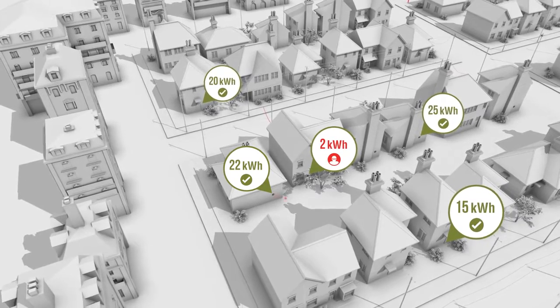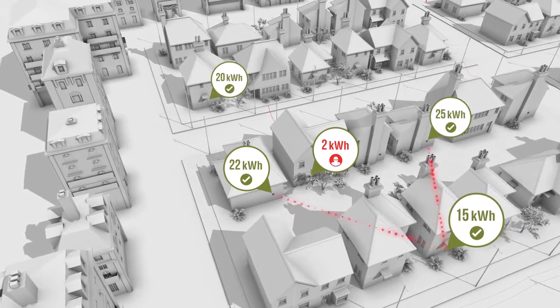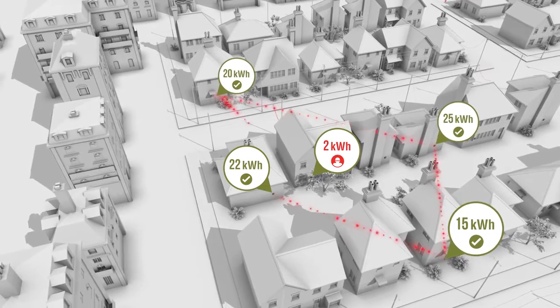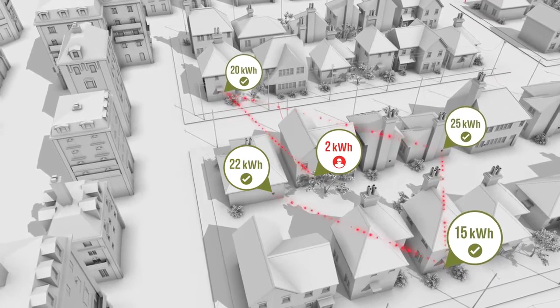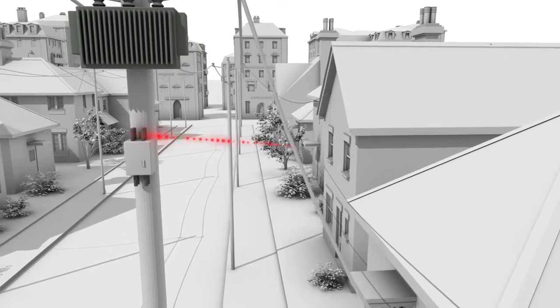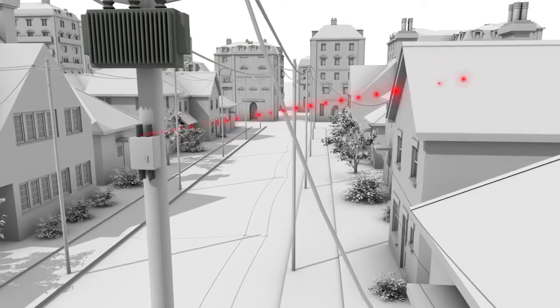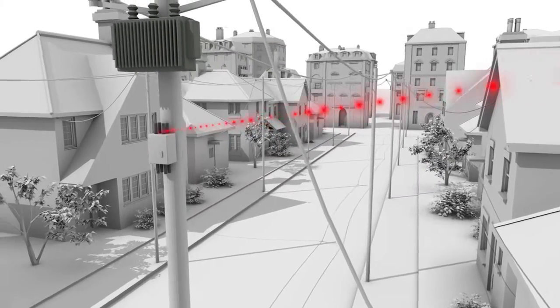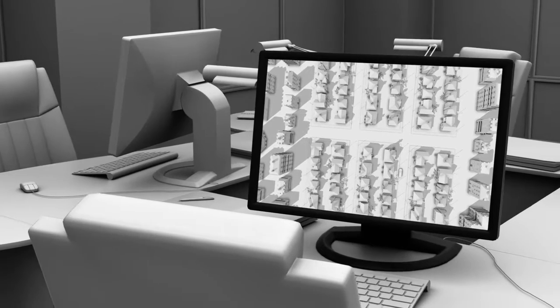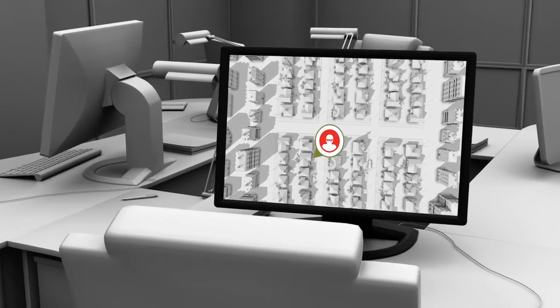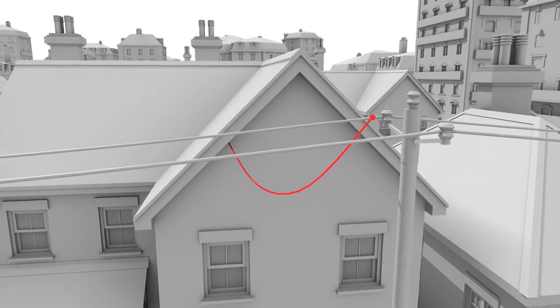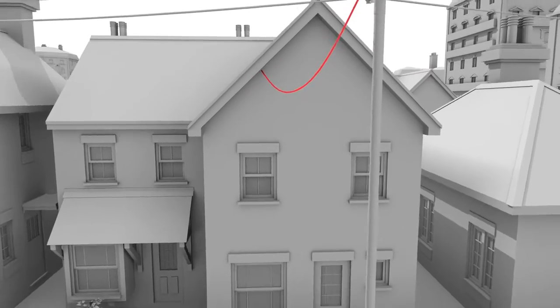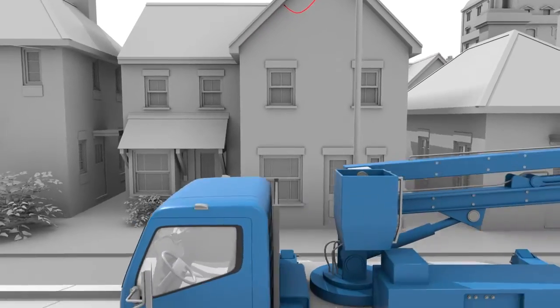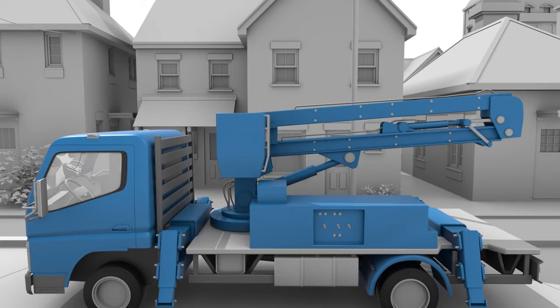It communicates locally between meters, calculates aggregated transformer loads, and knows exactly where those loads are on the distribution system. Only OpenWay Riva distinguishes instantaneously between legitimate electricity consumption and theft. With timely, accurate diversion detection, OpenWay Riva empowers investigative teams to act quickly and with greater precision to recover lost revenue and deter future theft.